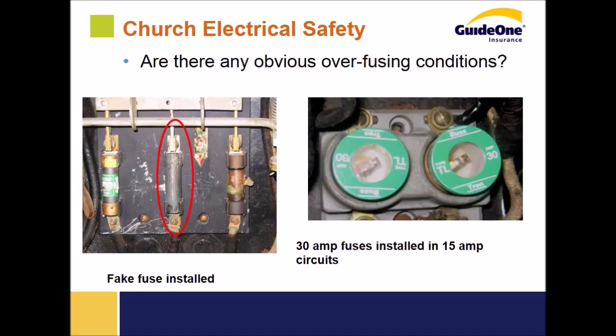The picture on the left shows an obvious overfusing condition. You've got a fake fuse installed. It's actually a little section of pipe that has been put in place. And you can see too that the fuse on the right has been hot, so we have a serious issue here. We don't expect you to view this type of thing, but it helps emphasize the need to have a licensed electrician come in. You don't know what's behind those panel covers, and periodically we need to make sure that our churches are having the appropriate review done to make sure their system is safe. Then the image on the right is simply an example of a 30 amp fuse being installed in a circuit that should be equipped with 15 amp protection.